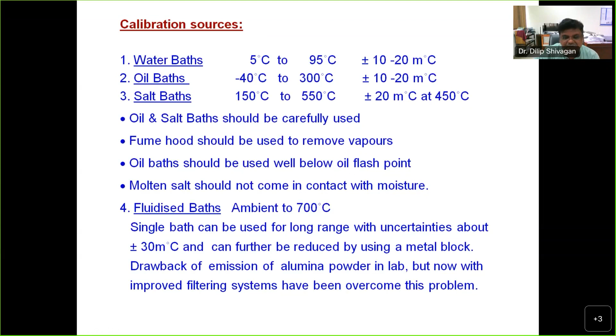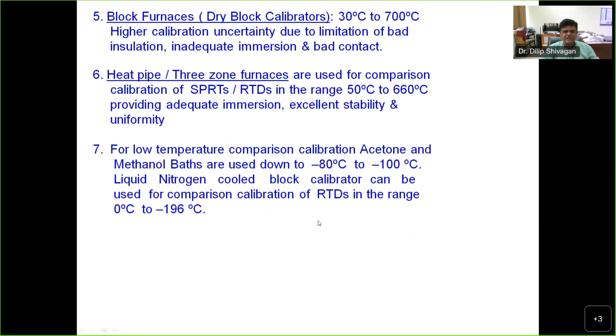So water bath is used up to 95, oil baths from minus 40 to 300, salt bath one can even go up to 550, and alcohol baths are being used up to even minus 90 degrees Celsius. So all these need some precautions like fume hoods for oil baths, and there is the worry of oil flash point, because after a certain temperature the oil itself will start burning. So those precautions you have to take into account before establishing the laboratory. Dry blocks can go up to 700 degrees Celsius. For thermocouples with a larger immersion, we can have up to even 1200 or higher. So heat pipe furnaces and low temperature, these also offer quite a lot of opportunities.